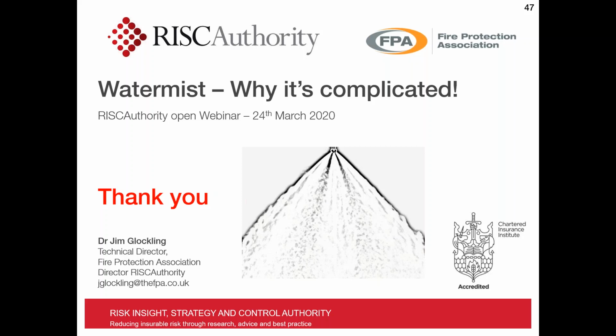However, I think the crucial thing here is to think about the protection that you're trying to afford and what you're trying to achieve at the end of the day. The starting point, particularly in a high-rise environment, is suppression systems are not a method for making up for poor building fabric and poor passive protection, which is missing or non-existent. I would argue that's probably a little more like putting lipstick on a pig. Any suppression system needs to have a good and appropriate passive envelope to perform within. So correcting the passive envelope is the starting point for all suppression system installations.